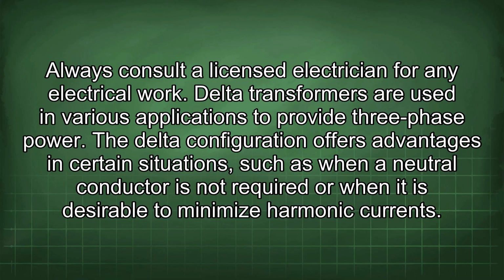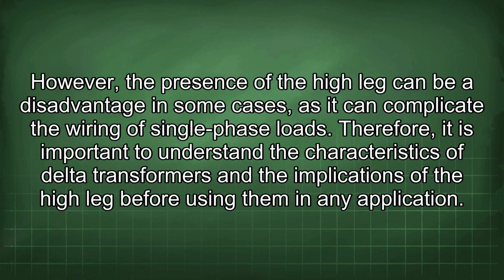Delta transformers are used in various applications to provide three-phase power. The delta configuration offers advantages in certain situations, such as when a neutral conductor is not required or when it is desirable to minimize harmonic currents. However, the presence of the high leg can be a disadvantage in some cases, as it can complicate the wiring of single-phase loads. Therefore, it is important to understand the characteristics of delta transformers and the implications of the high leg before using them in any application.